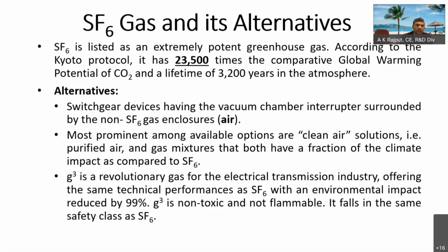So for 765 kV and 400 kV systems, these alternative gases are at present not available. But up to, say, 145 kV, there are rulings that in a phased manner, after a particular date, there will be no more SF6 based switchgear up to the 145 kV level. 245 kV voltage level switchgears are at the testing stage. The design has been completed and they are in the testing phase. And as far as gas insulated lines are concerned, 400 kV SF6 based gas insulated lines are in service, and there also, whatever alternative gases are there can be utilized in those gas insulated lines.